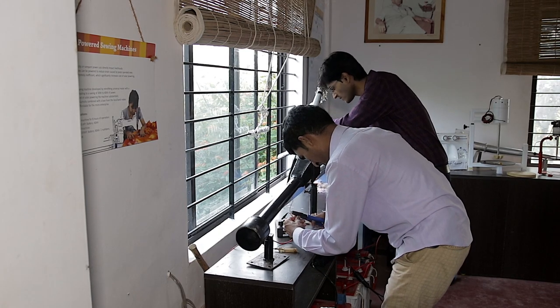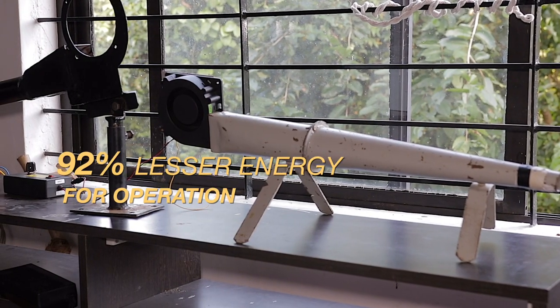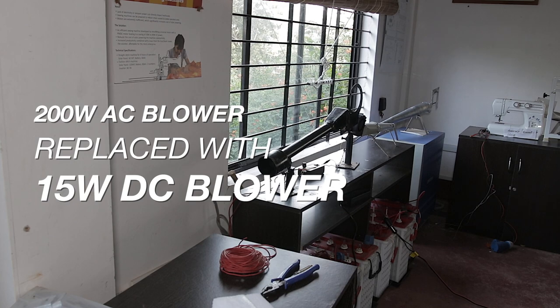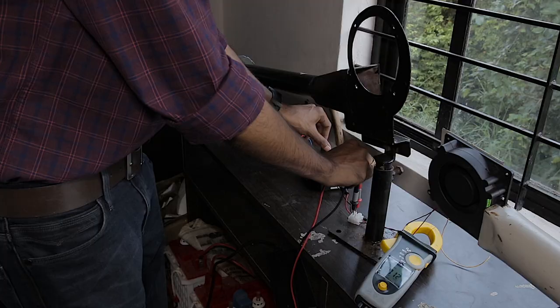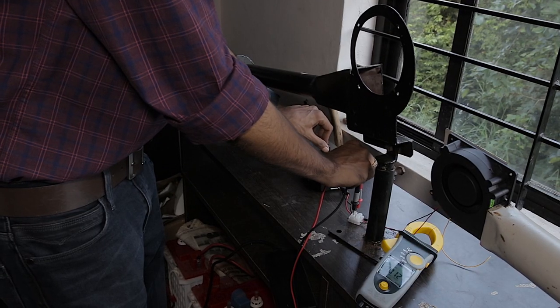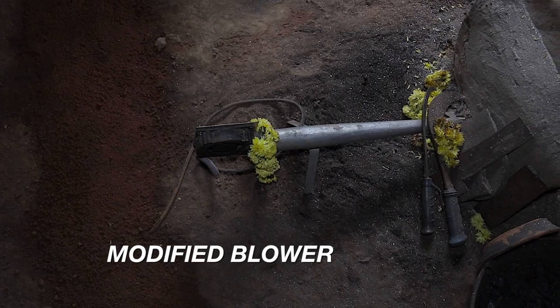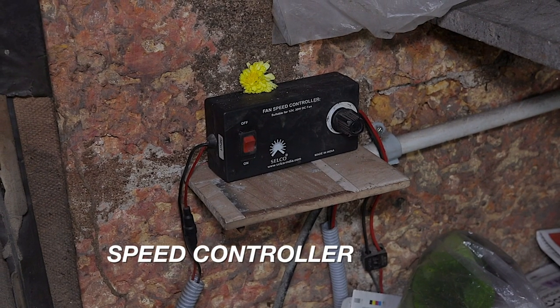Selco's rural community lab in Manipal developed an efficient, reliable, cost-effective solution which needs 92% lesser energy for operation compared to the motorized blowers available in the market. We looked at the airflow requirement, the RPM requirement, and the static pressure, and realized that the same 200-watt AC motor can be replaced with a 15-watt DC blower, which in a solar powering setup would cost around 15,000 rupees. The system consists of a modified powerful blower and speed controller for good airflow control.